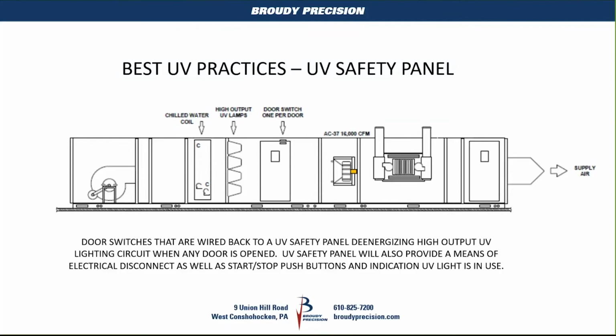And I'll just add, Ron, that if the door's open, lights are off, and when the doors shut, lights stay off until someone goes to this panel and says, I'm ready to turn the lights back on. So safety is the utmost concern there. Some of these rooftop units are really big, and the wattage on the UV bulbs is significant enough that if a technician were to look directly at it, he could really have problems. It's really a safety thing, and these are being installed in hospitals.